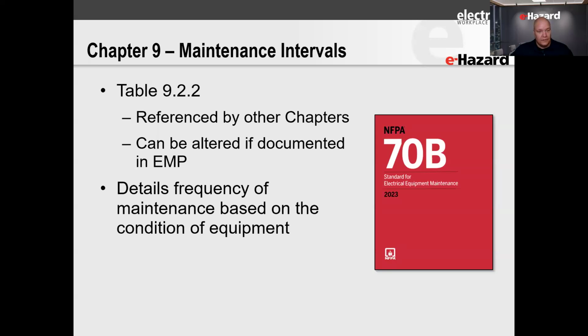I know one client of ours that I interact with regularly, they have a pretty good handle on maintenance of their equipment, but it doesn't work for them to shut down an entire plant every 5 years as 70B suggests. Because they're noticing there aren't as many issues with their equipment, they've extended it to a 7-year time frame where they do complete total maintenance of the entire plant. Everything gets maintained on a 7-year basis, but only because they've noticed they don't have any active indications or any parts where the equipment is in imminent failure.